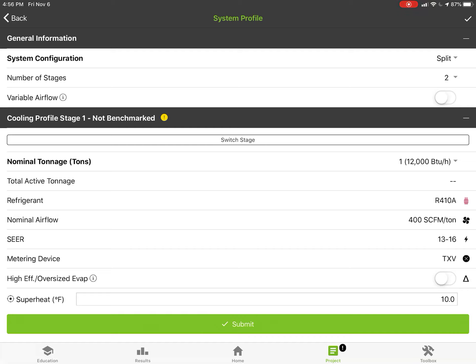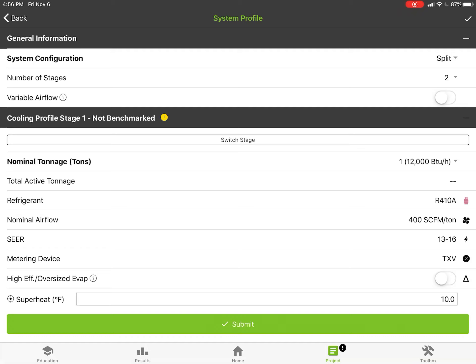This allows us, you know, we already have it set up here for two stages and we can switch it anywhere we want there. It allows us for variable or fixed airflow. Right now it's on fixed airflow, and that means that if we had a three ton system it'd be doing 1200 CFM. If it's two stages and it was like a ton and a half and ton and a half total three ton, it would always be doing three tons of airflow. That's real typical for rooftop units.